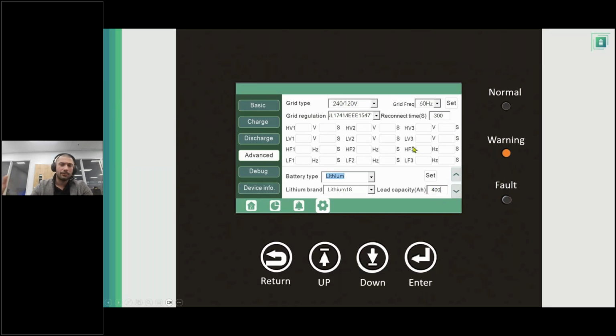The reason why I do this, you don't have to, but if for whatever reason there's an issue with the communication, the cable broke, somebody stepped on it, or you disconnected it, the system is going to default to the voltage settings. In the LCD it's called lead acid settings, but it's really just another word for your custom settings.